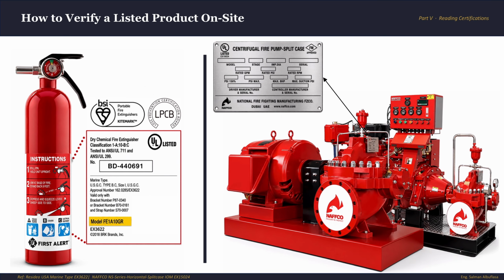Now, going back to the fire extinguishers, something I encountered in my field, and you will definitely do. You walk up to a fire extinguisher, you look at the label, and all you can see is tested according to ISO 7165 or manufactured according to ISO 9001. No UL mark, no LPCB, no third-party certification at all. Basically, ISO 7165 is the performance standard for portable fire extinguishers. It defines what the extinguisher must achieve: the safety requirements, the performance requirements, and the construction requirements.